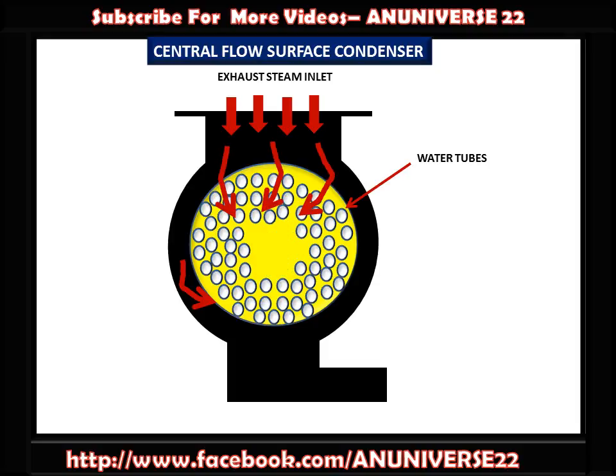The difference between the Central Flow and the downflow surface condenser is that in the middle of the water tubes there are no water tubes — basically there is a blank space for the entering exhaust steam. The suction pipe of the air extraction pump is placed at the center of the tube nest, so there are no water tubes in the middle.